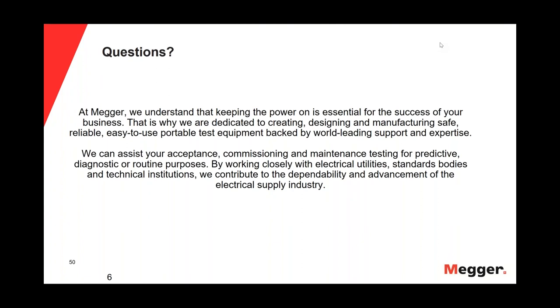Question for Javier: what are the differences between sine VLF and cosine VLF in terms of results? One of the big differences is that during a VLF test we try to convert defects into faults via electrical trees. During the polarity reversal for a sine VLF, that transition takes about five seconds. On the other hand, with cosine rectangular it happens in milliseconds. So we stress the cable more with the cosine rectangular wave shape than with the sine wave shape. For that reason, in terms of stress or in terms of replicating what happens at 60 Hz, the cosine rectangular wave shape is sometimes better.